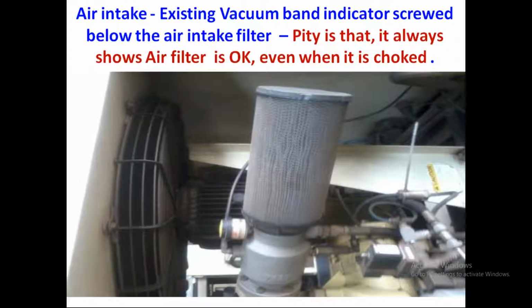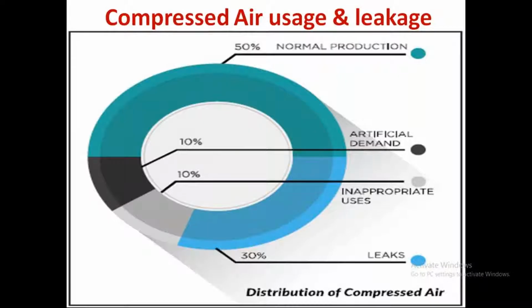We removed that filter, inserted our digital Pascal gauge and measured the Pascal. So instead of that, you put an impulse connection and take it outside the hood and just leave it like that. This IoT device will show the compressor is healthy daily. This is what is wanted now. This is a 160 kilowatt machine, and here the Pascal is not monitored, which means it is a loss to the system. Accelerated aging of the compressor can happen only because of a starved intake at the air intake.